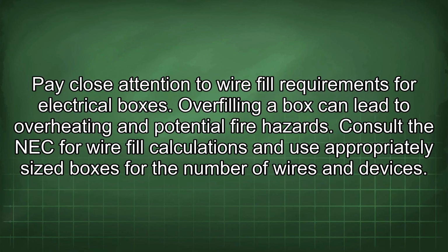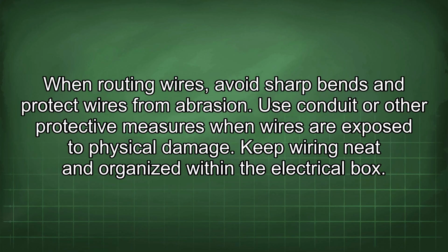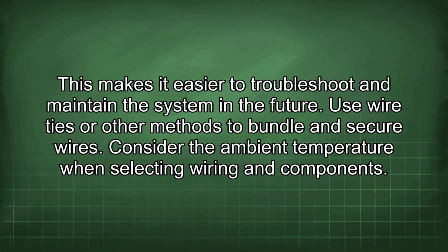Pay close attention to wire fill requirements for electrical boxes. Overfilling a box can lead to overheating and potential fire hazards. Consult the NEC for wire fill calculations and use appropriately sized boxes for the number of wires and devices. When routing wires, avoid sharp bends and protect wires from abrasion. Use conduit or other protective measures when wires are exposed to physical damage. Keep wiring neat and organized within the electrical box. This makes it easier to troubleshoot and maintain the system in the future. Use wire ties or other methods to bundle and secure wires.